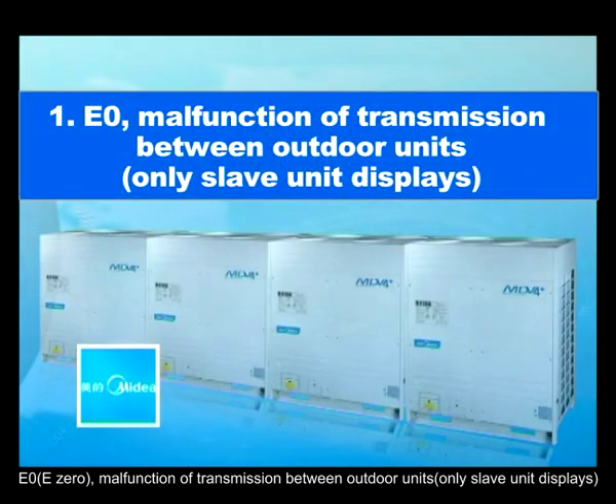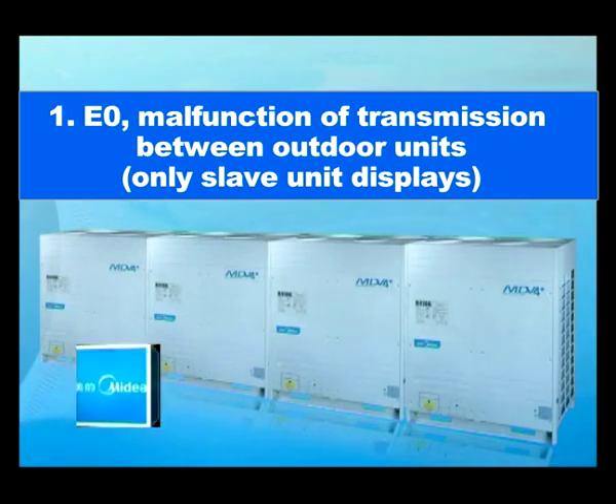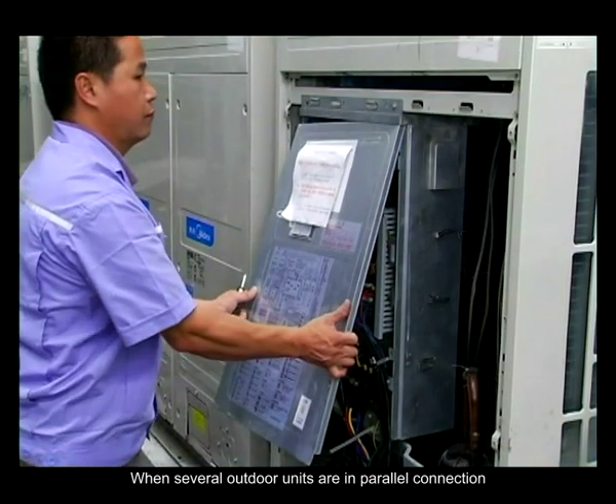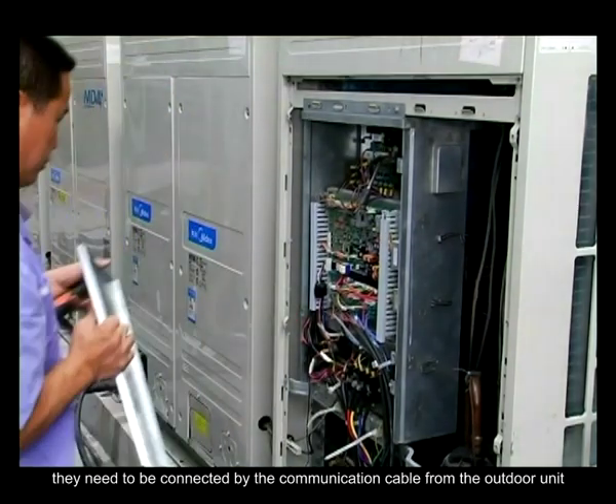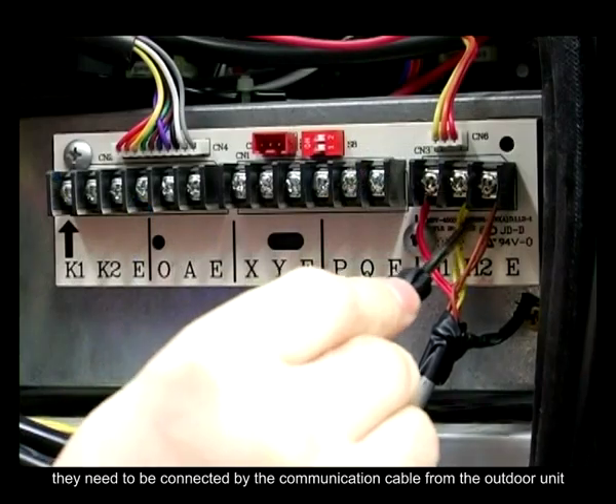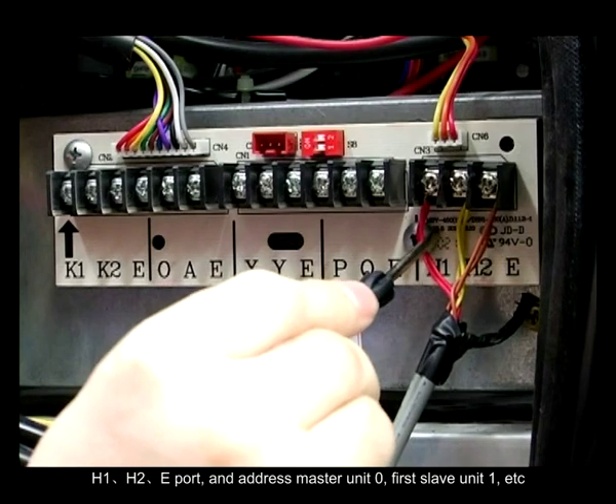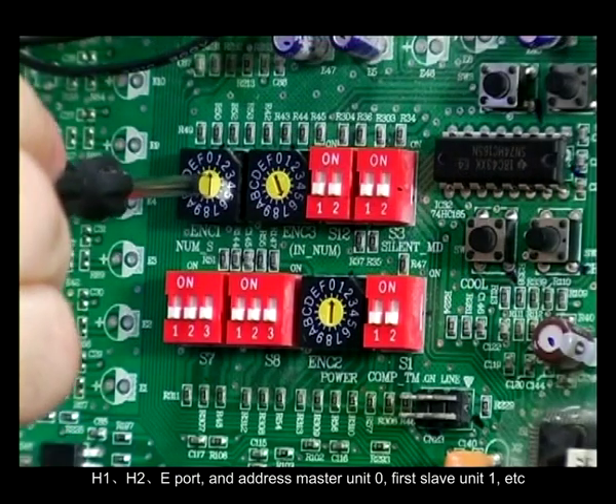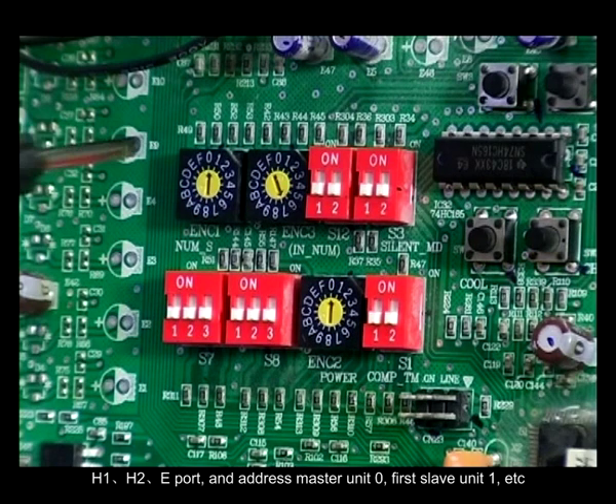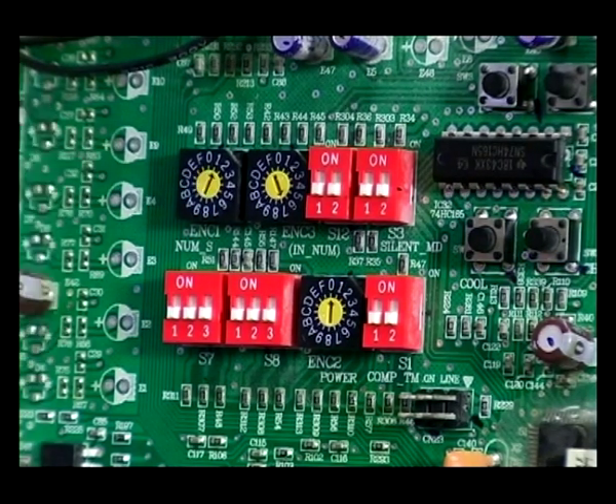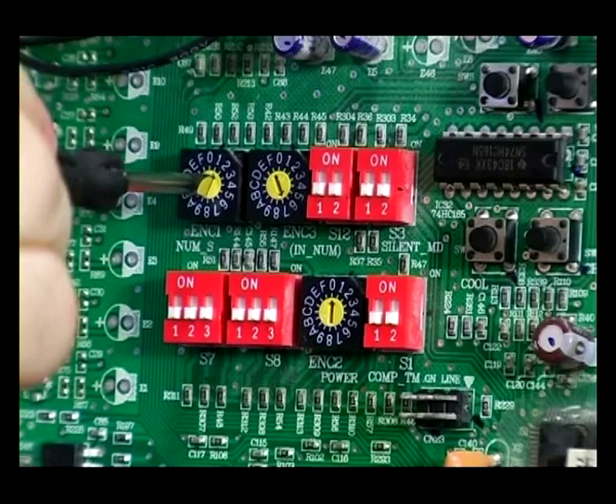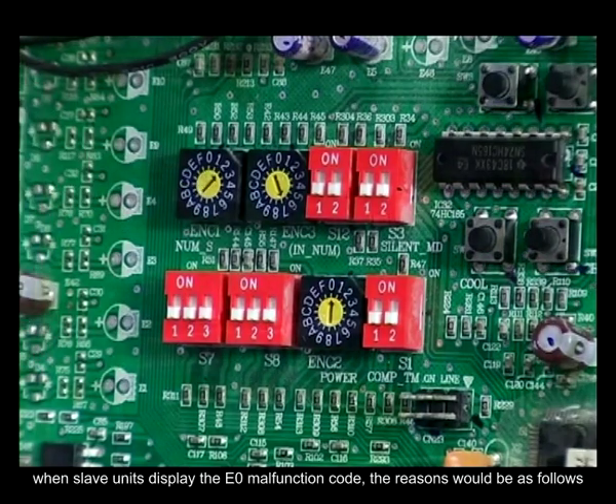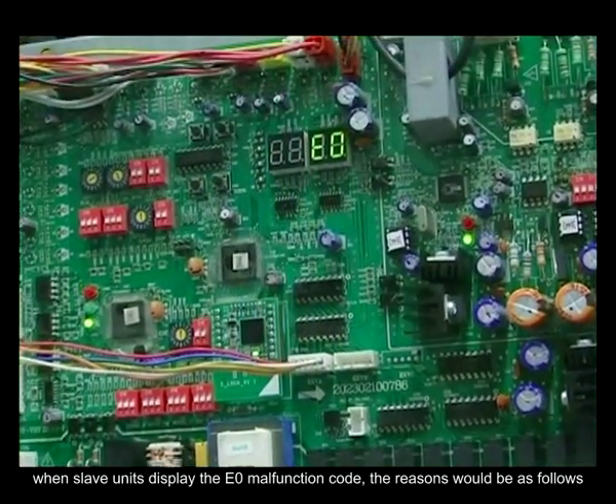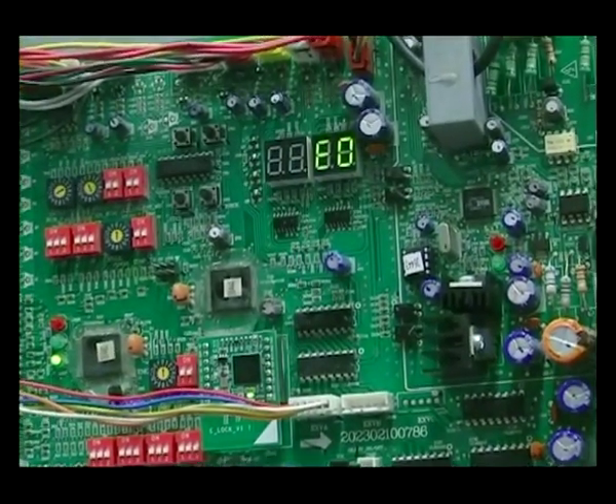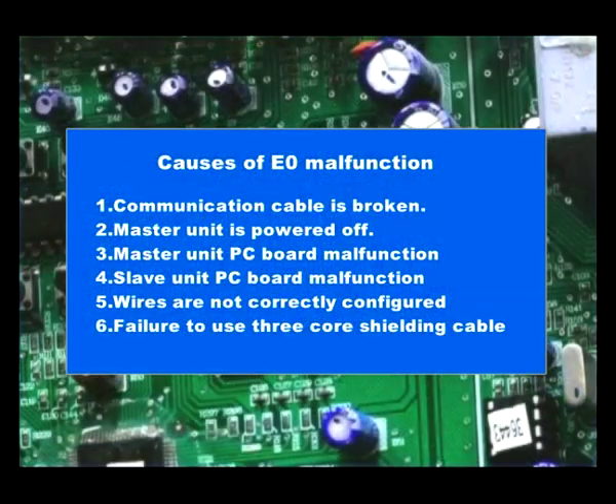E0. Malfunction of transmission between outdoor units. Only slave unit displays. When several outdoor units are in parallel connection, they need to be connected by the communication cable from the outdoor unit H1, H2, E-port, and address master unit 0, first slave unit 1, etc. When slave units display the E0 malfunction code, the reasons would be as follows. Cause of E0 malfunction.